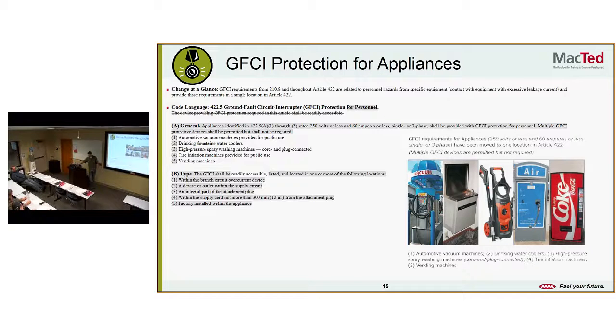Okay. GFCI protection for appliances. GFCI requirements from 210.8 through Article 422 are related to personnel hazards from specific equipment, contact with equipment with excessive leakage current, and provide those requirements in a single location in Article 422. Looks like they've, what did they add here? Appliances identified in 422.5, which are 250 volts or less and 60 amps or less, single or three-phase, shall be provided with GFCI protection for personnel. Multiple GFCI protection devices shall be permitted but not required.